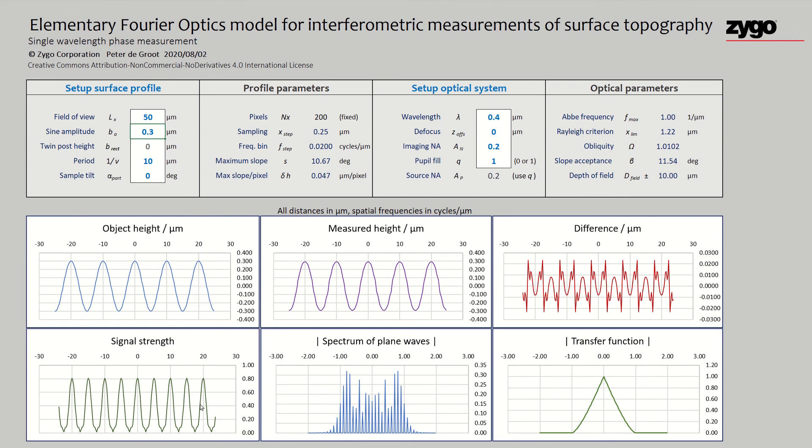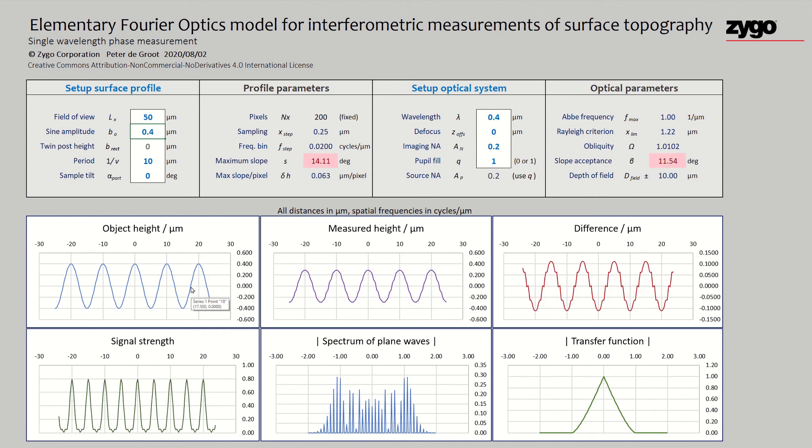The slopes here are so high that we're actually approaching zero signal level. If you really did this in an interferometer, you would start to see some dropouts at the high slopes. Matter of fact, if we keep going, the worksheet will flag that you have exceeded the slope acceptance of the instrument. That's determined by the numerical aperture.